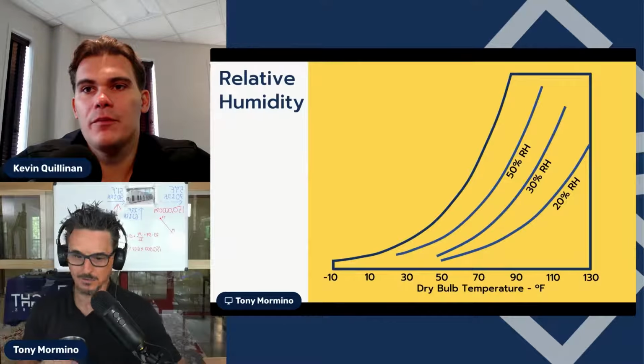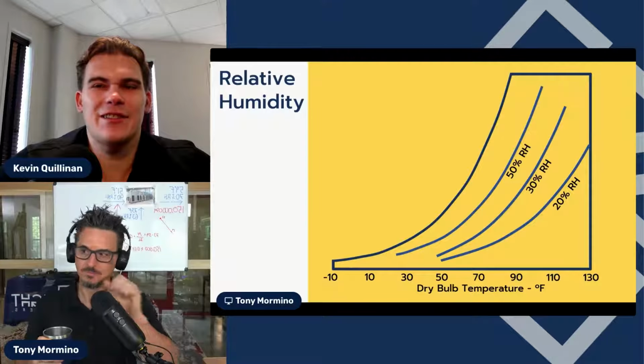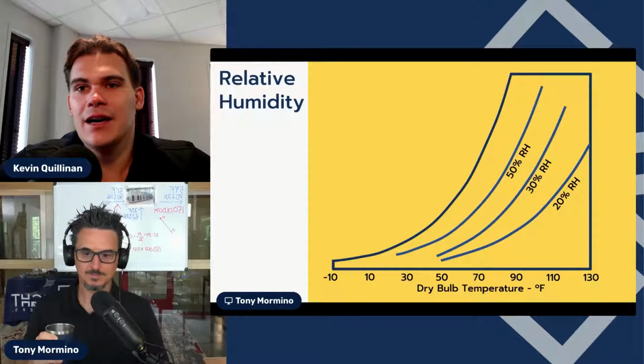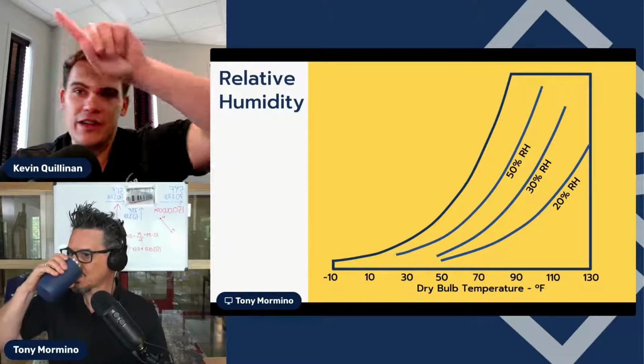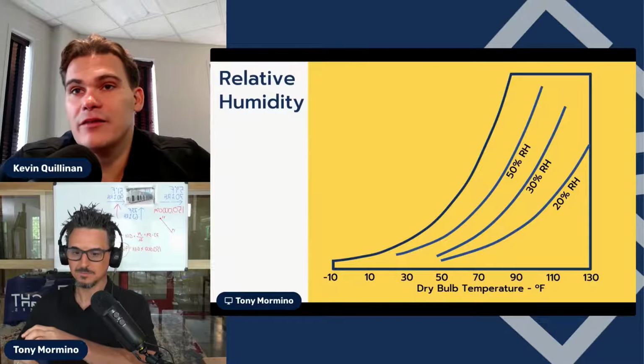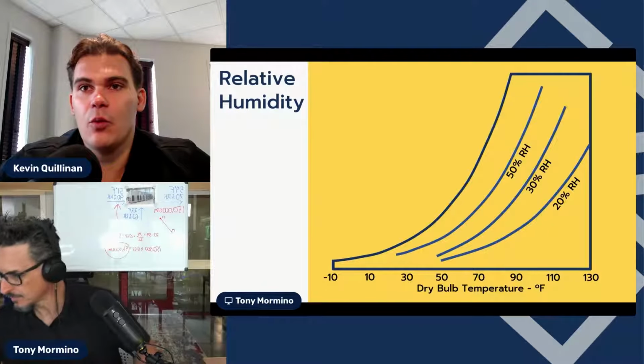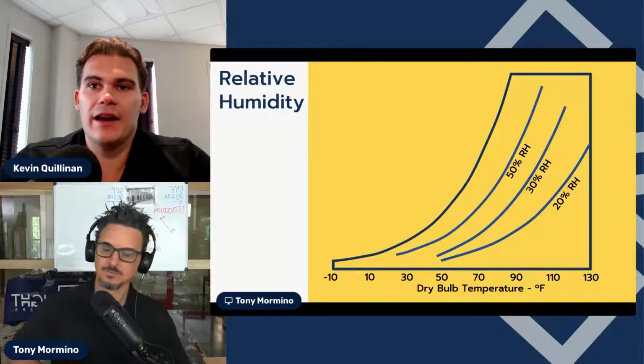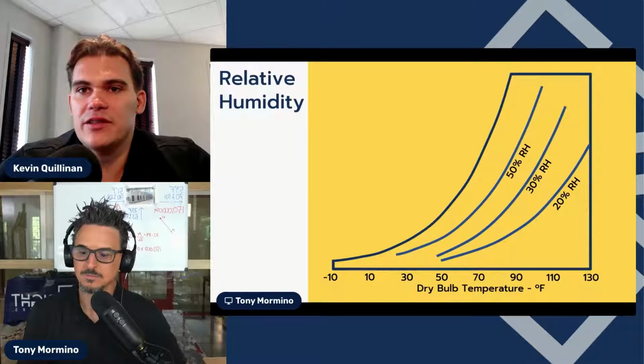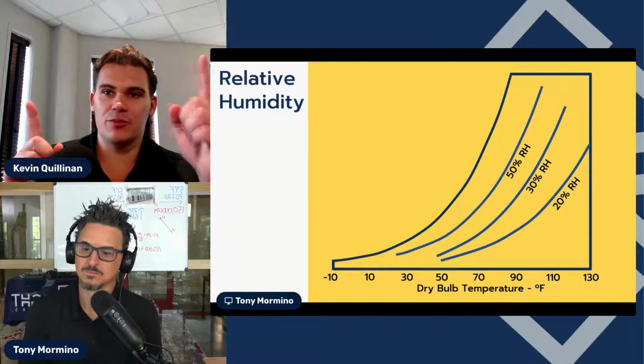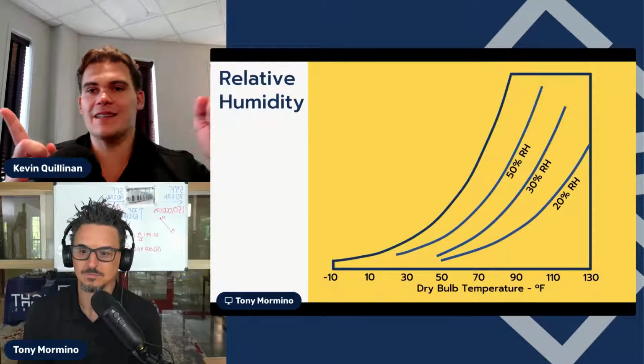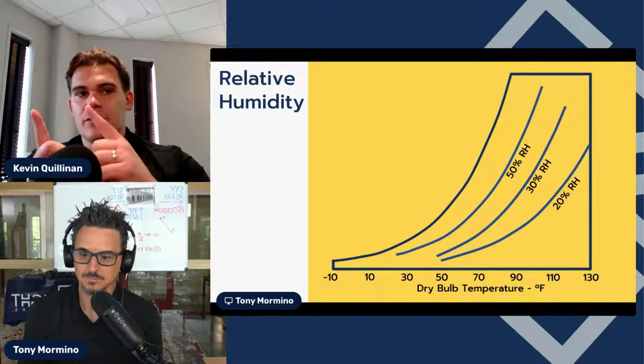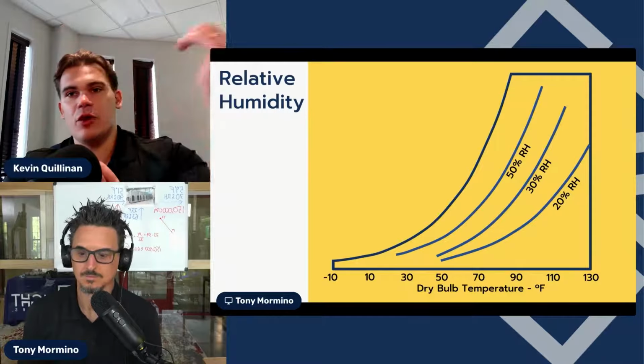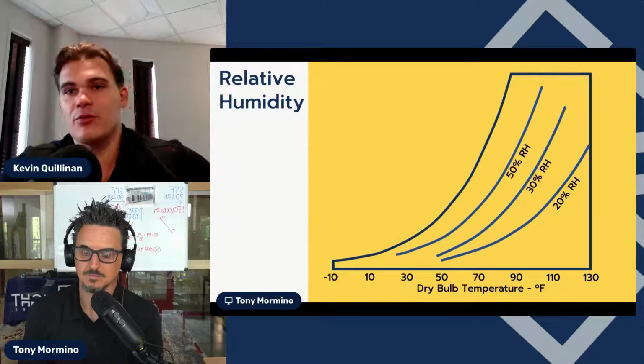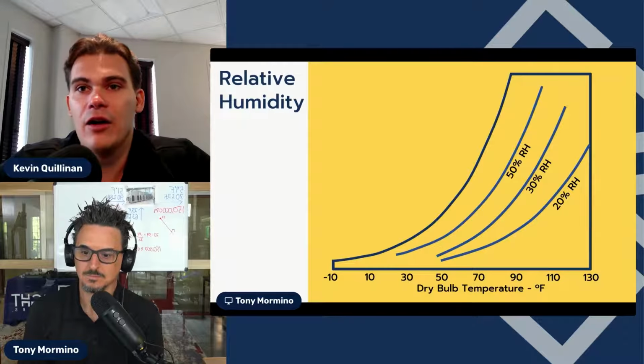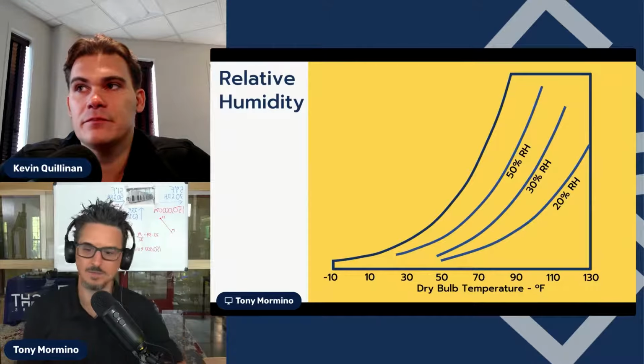And what about these lines here? Yeah, so relative humidity lines, and I feel like these are what really make that chart look so busy, these swervy lines going throughout the chart. What's cool about the relative humidity lines is, if we look at our wet bulb line, the way they define these lines was between 100% relative humidity and 0% relative humidity. That's how far along you are on your wet bulb line. So that's why you have this curve. If you were on the 50% relative humidity line, it would be exactly halfway on that wet bulb line. Got it.